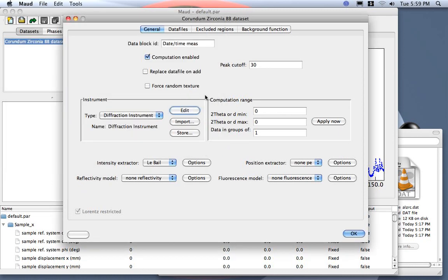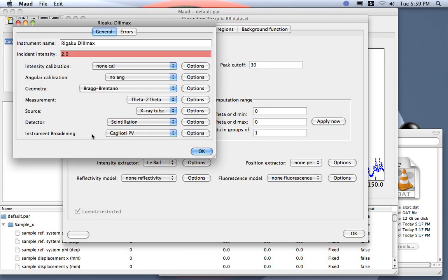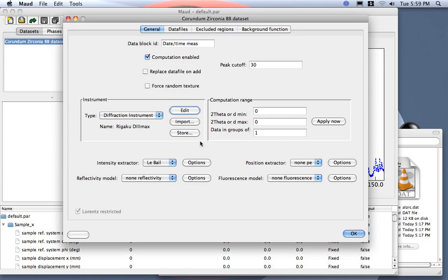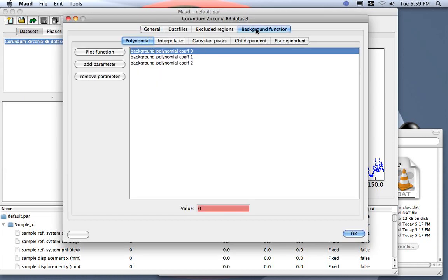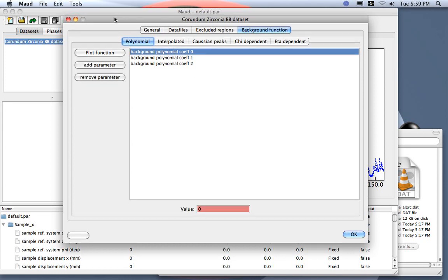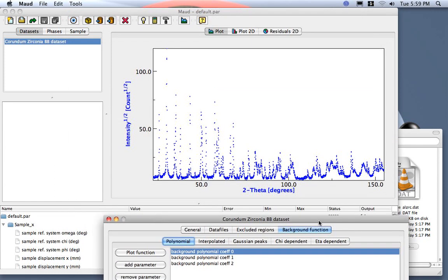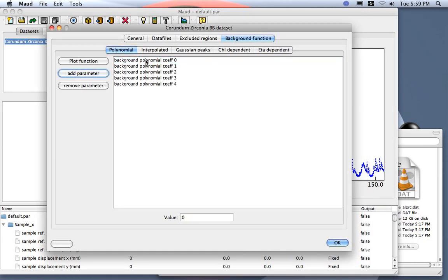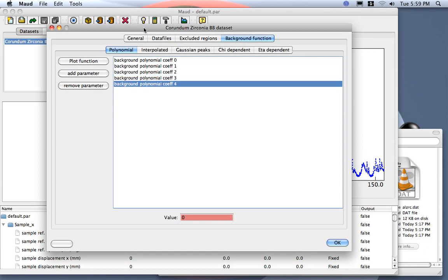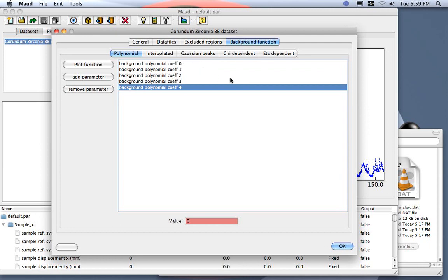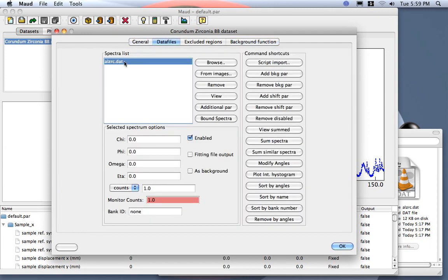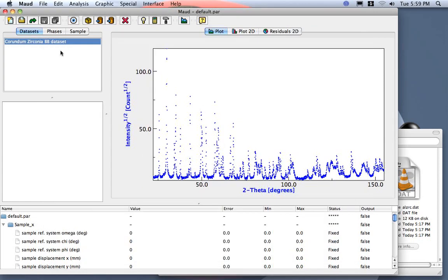In reality, okay, we don't need to modify anything, because here, in the instrument broadening, this was already set for this instrument. Okay, there will be another lesson showing how to calibrate this instrument to measure the instrument broadening defined in MAUD. Okay, now we only want to change maybe the background. So by default, here we have 3 coefficients, and maybe because we have a large pattern here, you see more than 120, maybe we just choose to use a polynomial background of 5 coefficients. Okay, the rest we leave as it is. So we have a data file, and we have just modified the background.